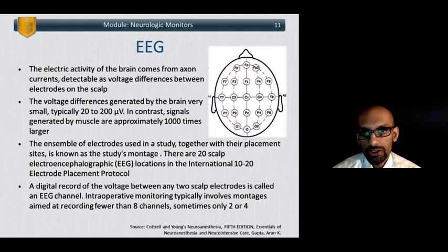So, moving on to formal EEG. This is where you use multi-channel EEG. You're watching the electrical activity not just of the frontal lobe, but across the entire spectrum of the cortex. Overall, whether you're using processed EEG or raw EEG, multi-channel or single-channel, you need to understand that the voltage generated by the brain is very small, about 100 times less than that of an EKG. So these recordings are very susceptible to interference due to myopotentials from muscular contractions or general myotonicity, electrocautery, and so on and so forth.